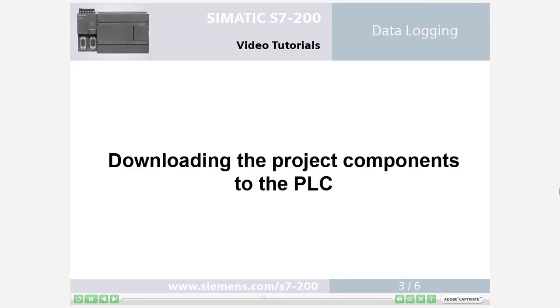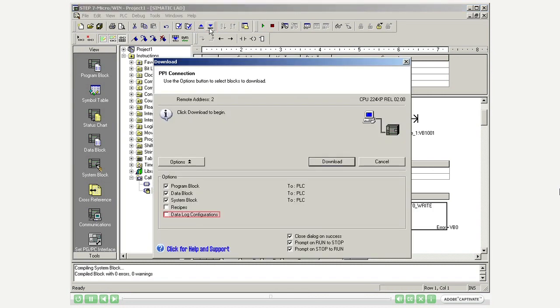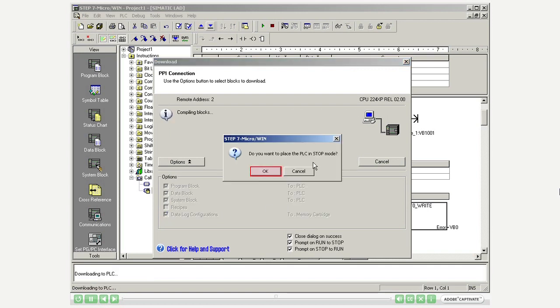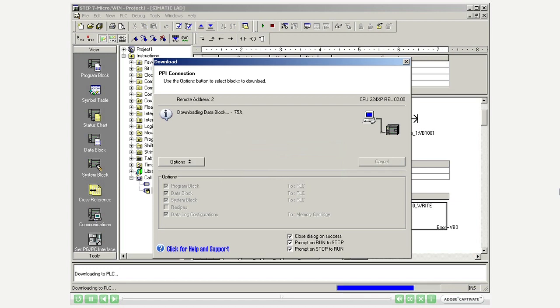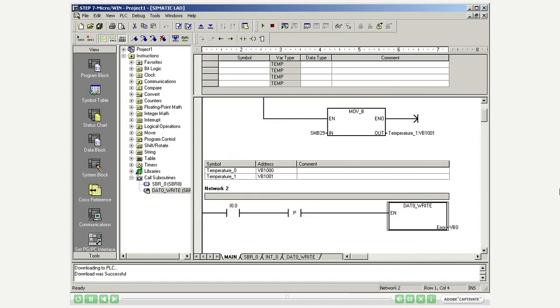Step 3: Downloading the project components to the PLC. Download the project to the PLC. Select in the download options also the data log configurations. Stop the PLC to transfer the data. Place the PLC in run mode again.